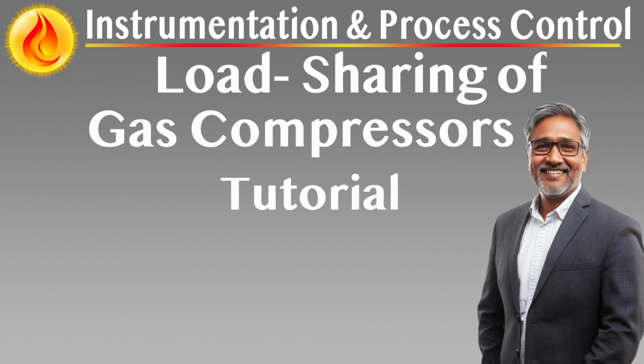2. Compressor network moving towards surge. The unit with the highest recycle demand maintains its normal surge protection response. The other compressors open their valves more gradually to catch up and avoid lag in response. Ensures no single compressor bears the full load of surge control.